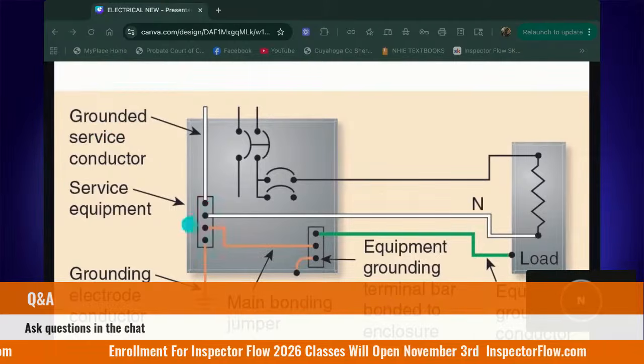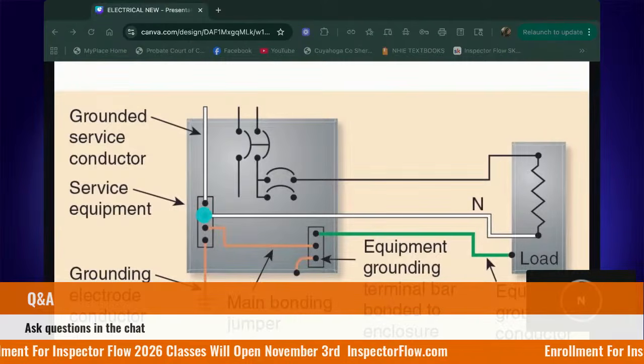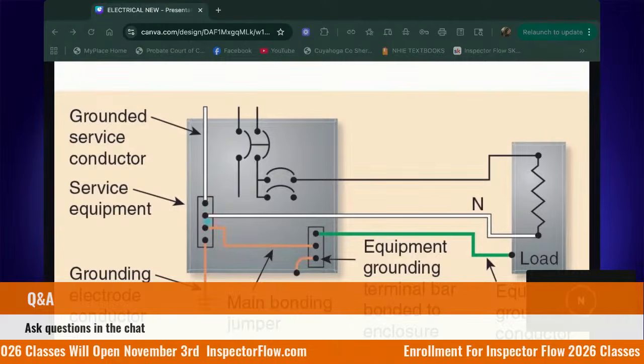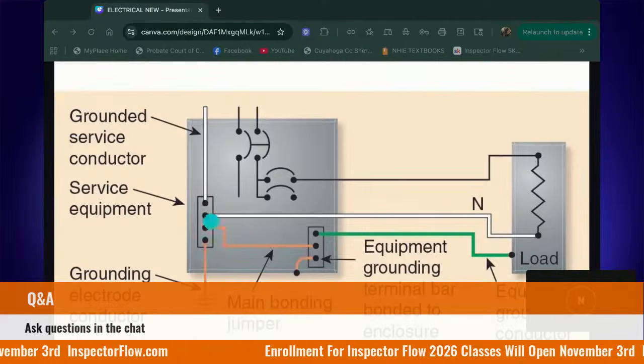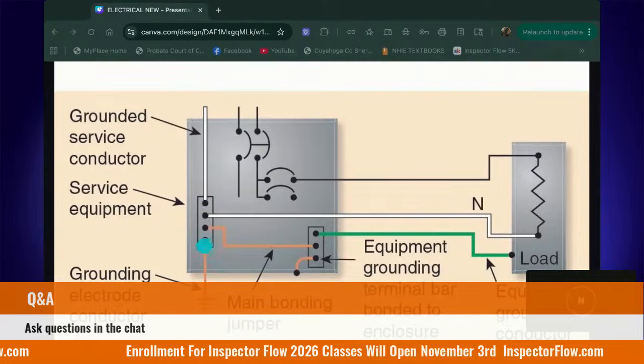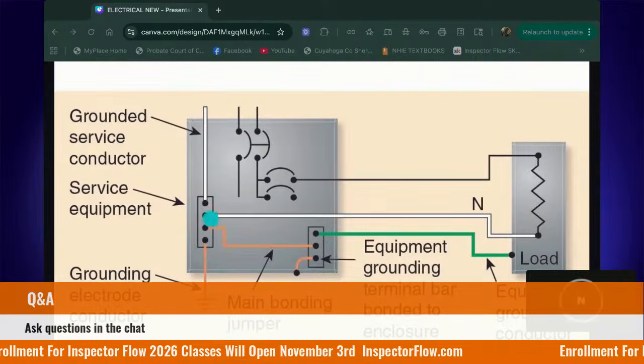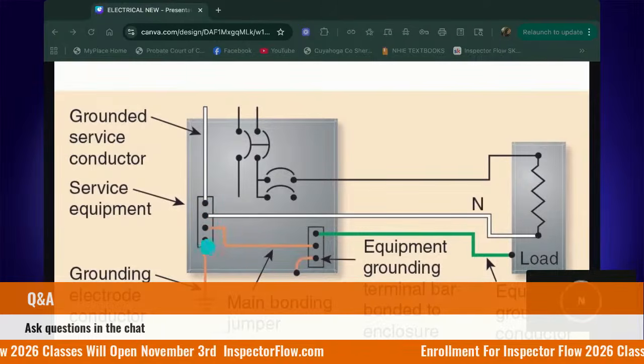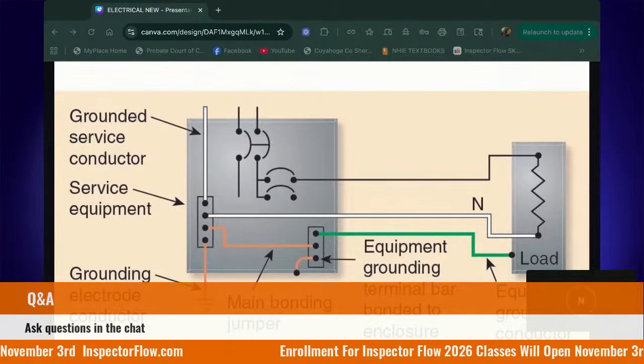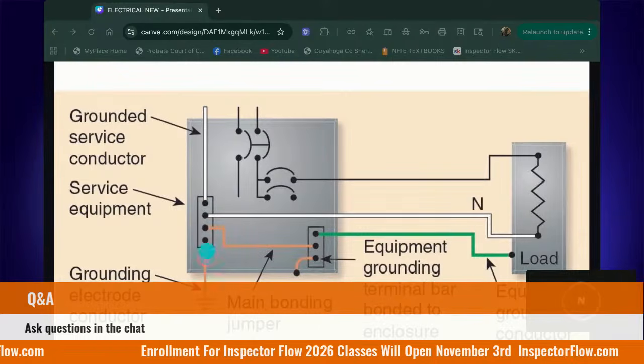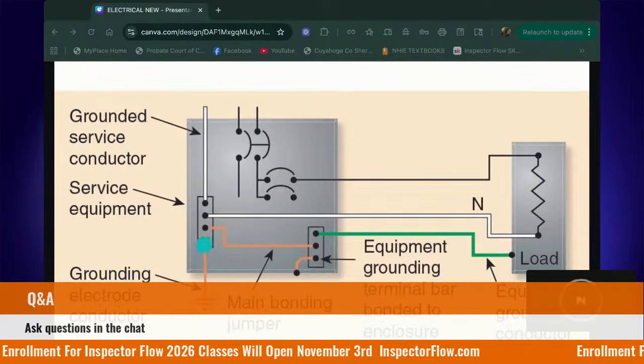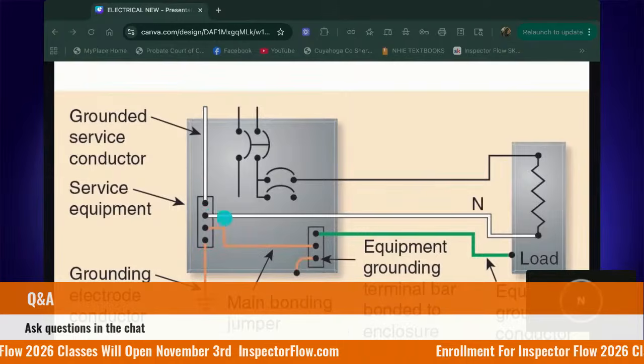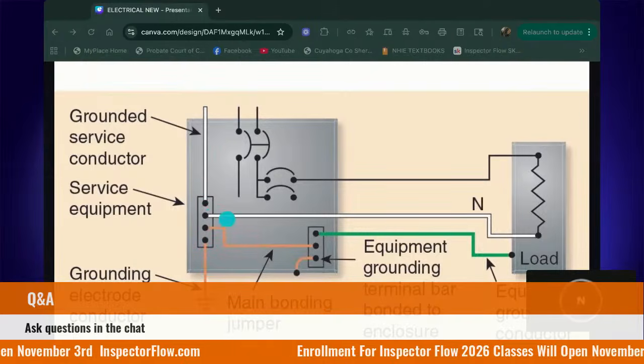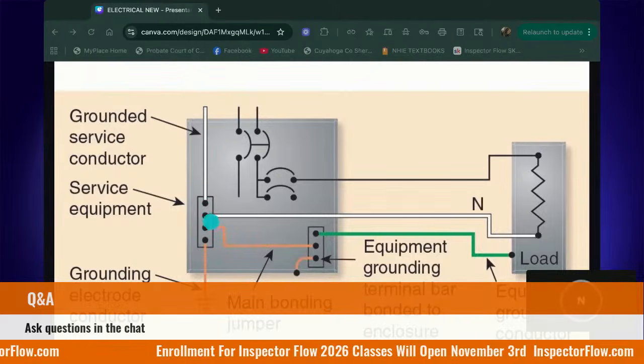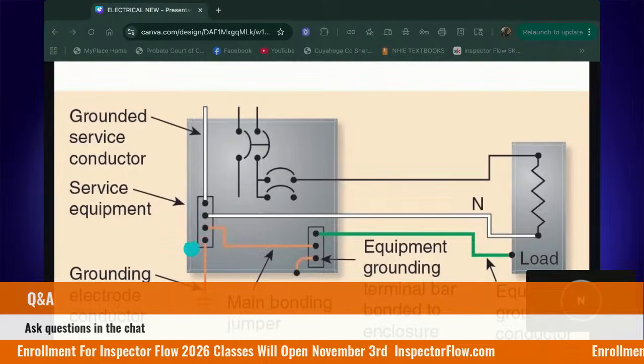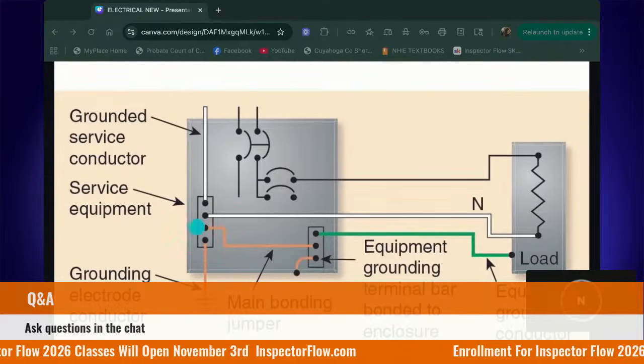And so, what type of bus bar is this? It's a main panel. What type of bus bar is this? Neutral grounding bus bar. Just a neutral bus bar, because as far as we can see on this diagram, there's only a neutral wire. Okay, so if it's only neutral wires terminating on it, it is a neutral bar.